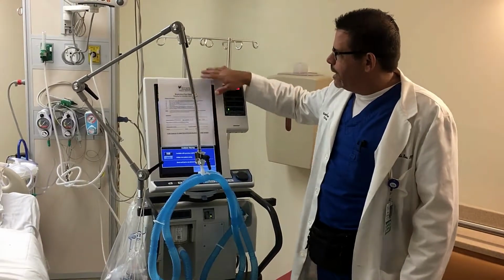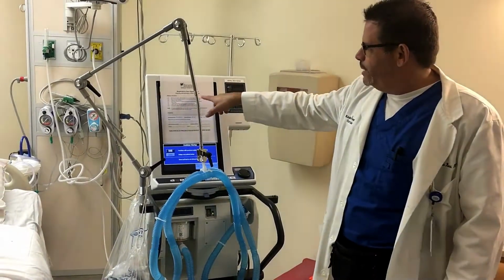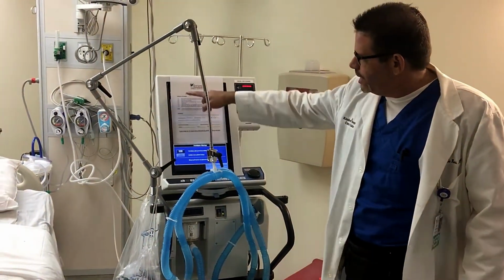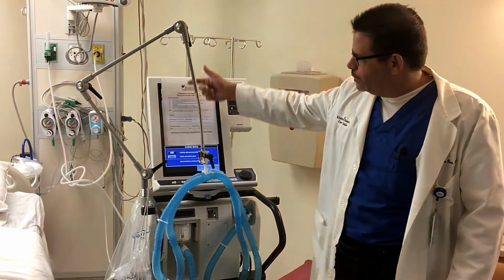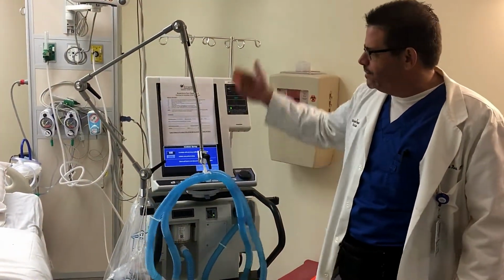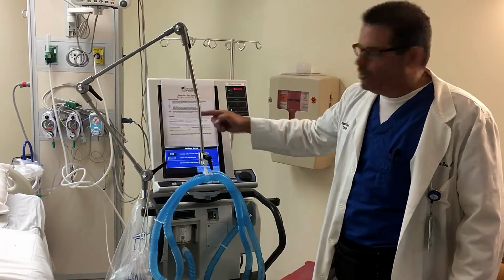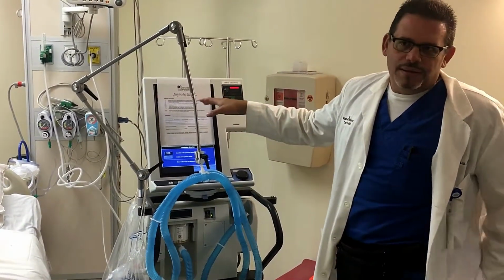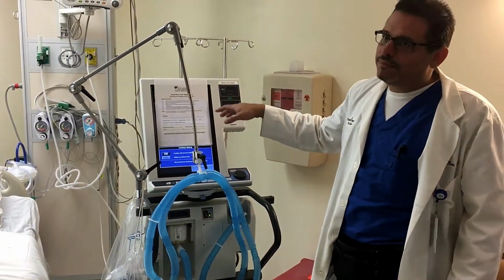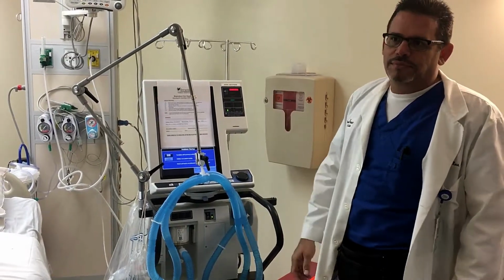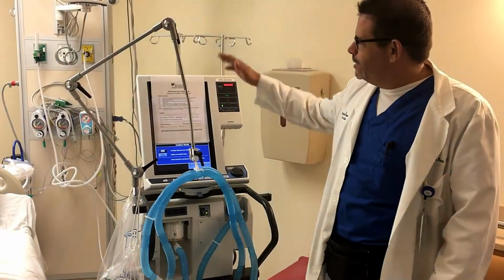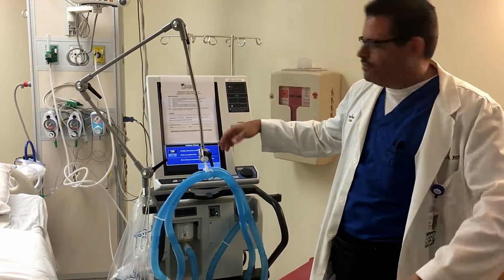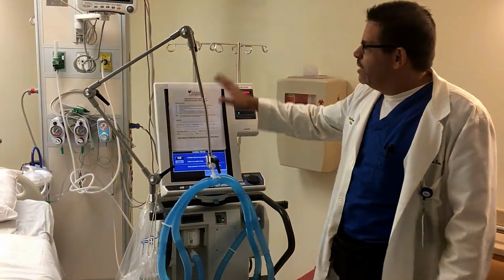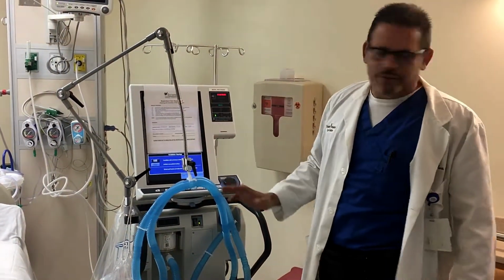I have been filling these out, which is the cleaning and assembly of the 840 ventilator with the whole checklist of everything that they checked on it, that it was calibrated, that everything was replaced. That ventilator serial number. This machine is a life or death machine. So it's like the OR. You have to have a check-off list. Make sure there's nothing going wrong. Was this checked? Was that checked? Everything's monitored by OSHA, by the government, by the Joint Commission. So it's all regulation issues, okay?